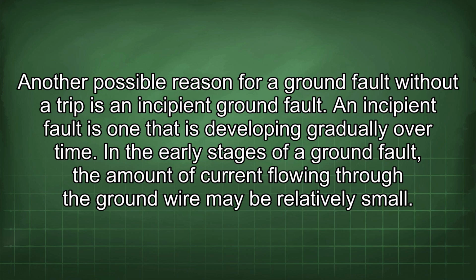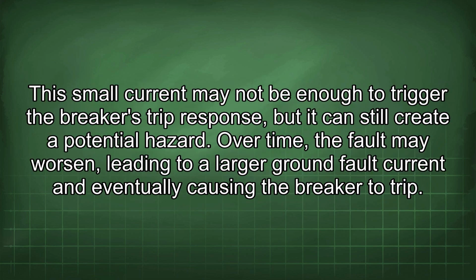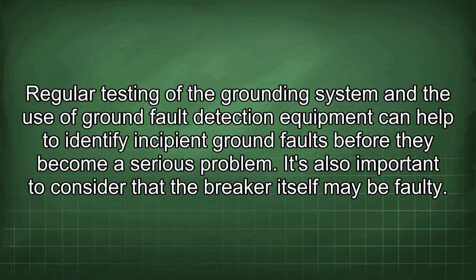Another possible reason for a ground fault without a trip is an incipient ground fault. An incipient fault is one that is developing gradually over time. In the early stages of a ground fault, the amount of current flowing through the ground wire may be relatively small. This small current may not be enough to trigger the breaker's trip response, but it can still create a potential hazard. Over time, the fault may worsen, leading to a larger ground fault current and eventually causing the breaker to trip. Regular testing of the grounding system and the use of ground fault detection equipment can help to identify incipient ground faults before they become a serious problem.